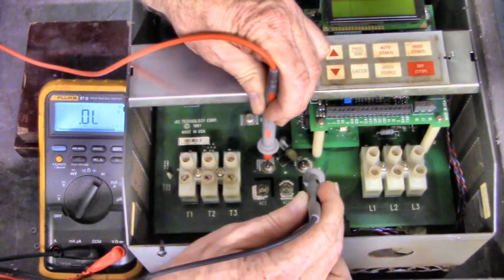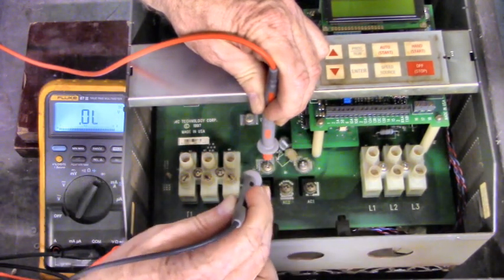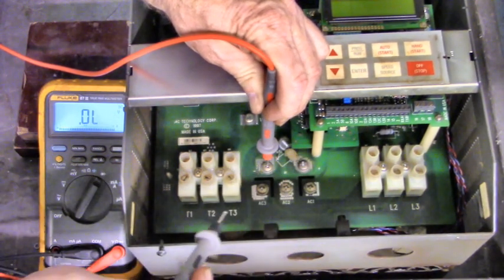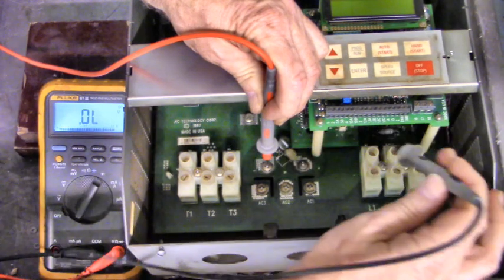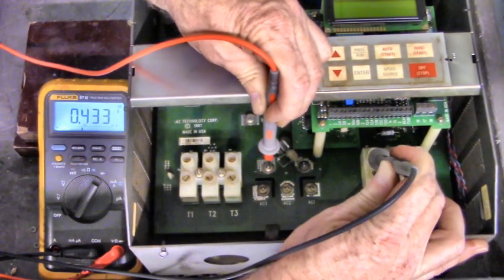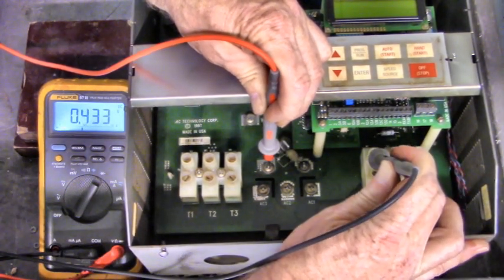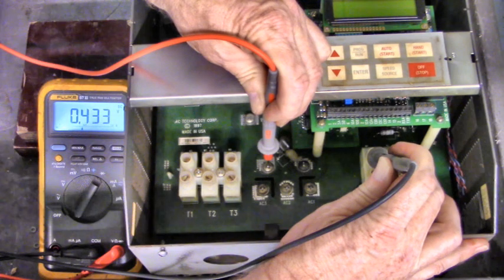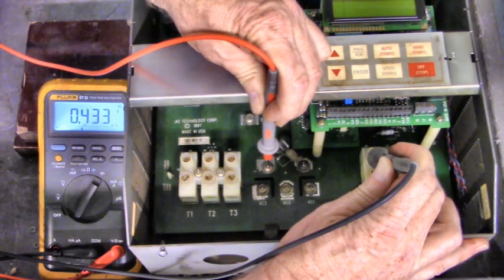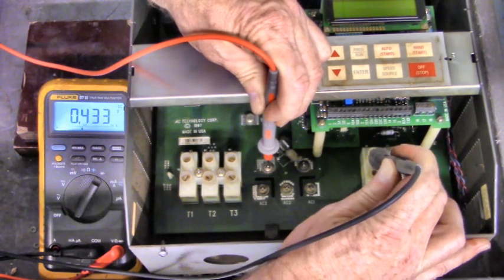This might be labeled P, and that might be labeled N on your drive. Now, black lead on L1. There we have good diode voltage drop of .433.